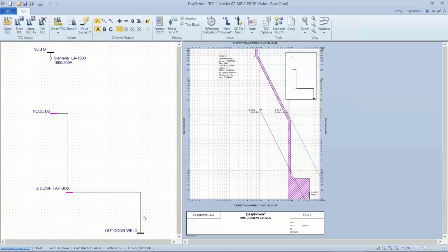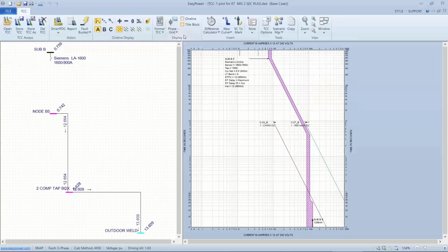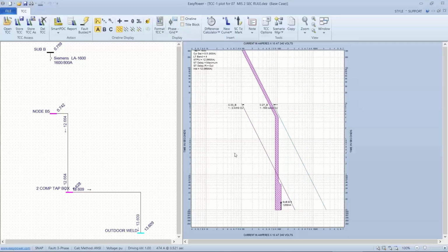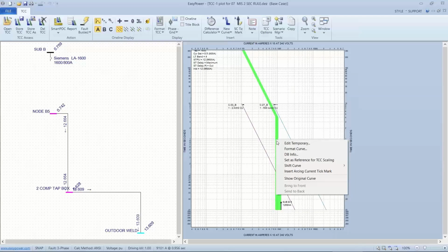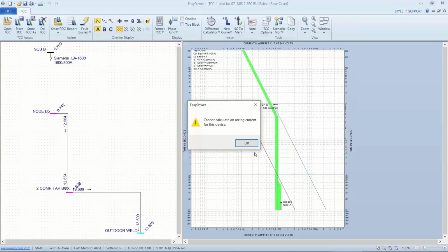And that is, if I have a fault on this bus, my short circuit current does indeed trip the breaker that's upstream. But that's on a bolted fault current. What happens if I have an arcing fault? Well, to see the arcing current, I hover over the plot for the breaker, for the device that's tripping, and I right-click and insert arcing.